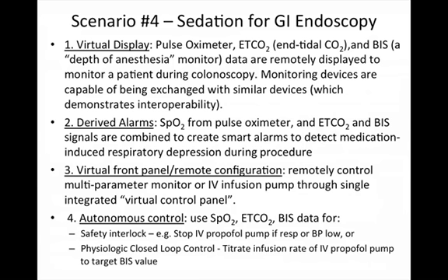The second level of the scenario is one in which we use derived alarms. So in this case, we would take data from the pulse oximeter, from the end-tidal CO2 monitor, and from the depth of sedation monitor, and combine that data in such a way that we could create a smart alarm to provide earlier detection of medication-induced respiratory depression during the procedure.